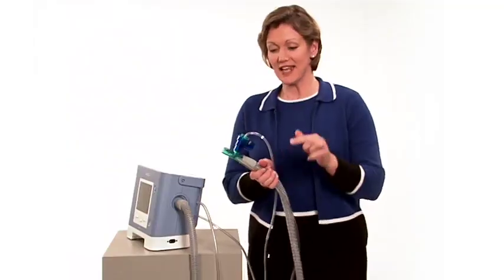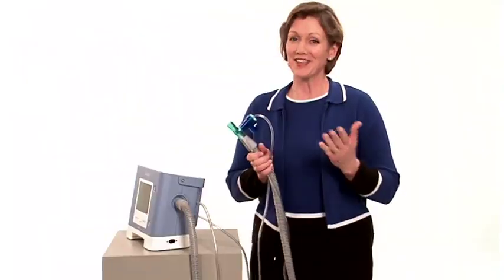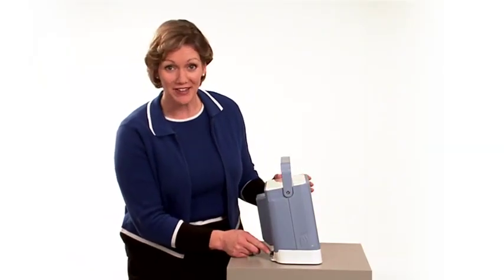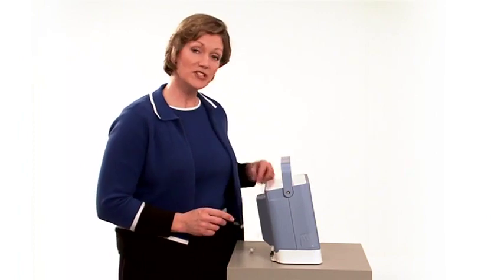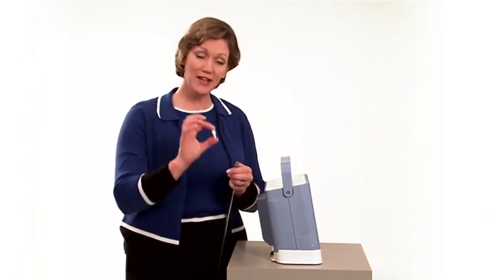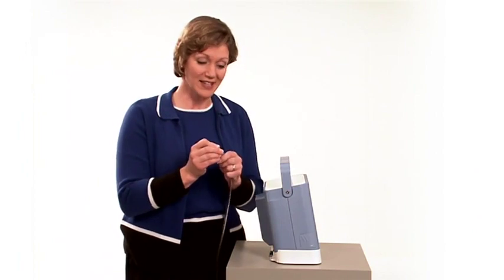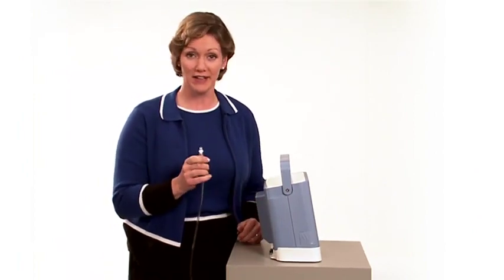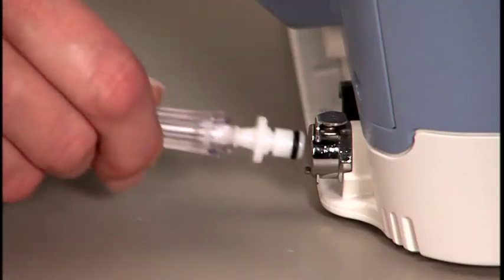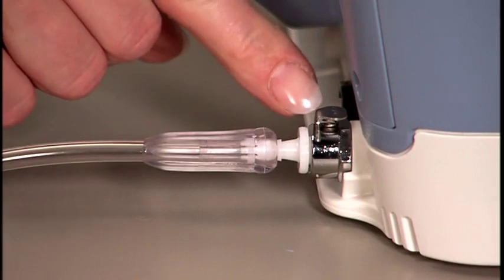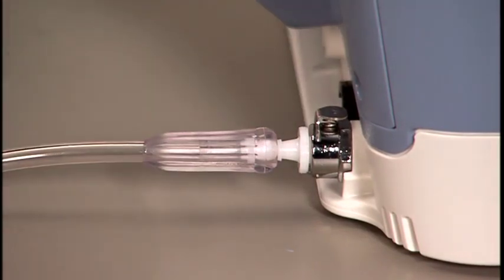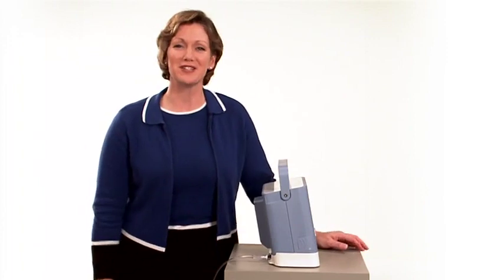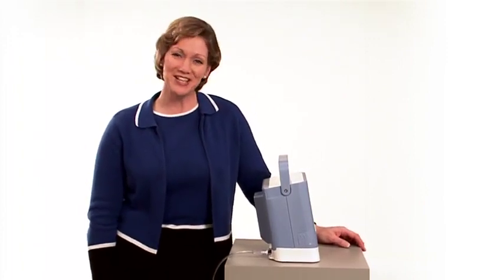The other end is connected to the top of the exhalation valve. The active circuit is now connected. If the physician has prescribed supplemental oxygen, that port is here on the back of the device. Connect the oxygen tubing to an oxygen valve Quick Connect. Attach the Quick Connect to the oxygen valve inlet on the back of the ventilator. Make sure you press the oxygen valve Quick Connect firmly into the inlet. You should hear a click and see the tab at the top of the port pop up. Once Trilogy 100 is set up, you're ready to turn it on and interact with the screens.